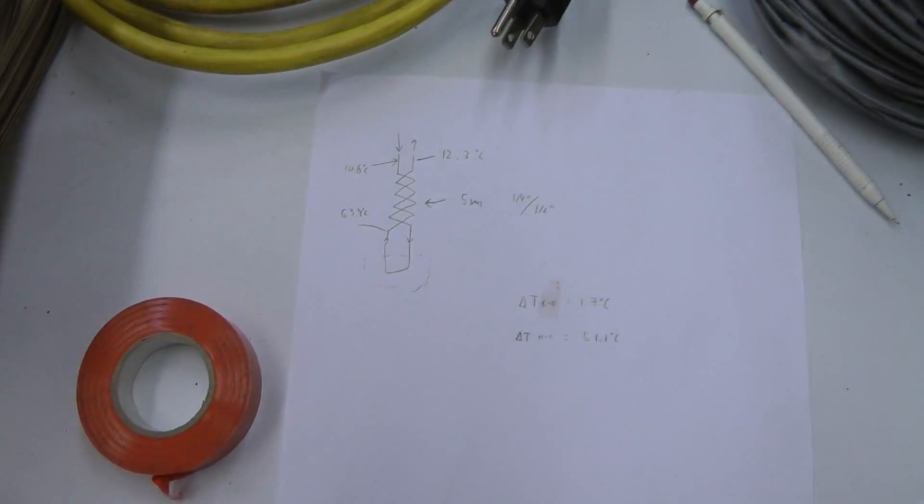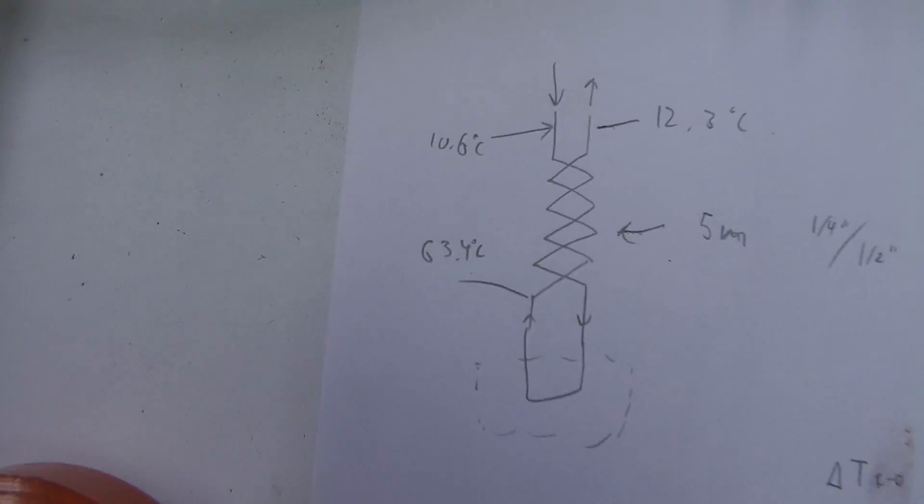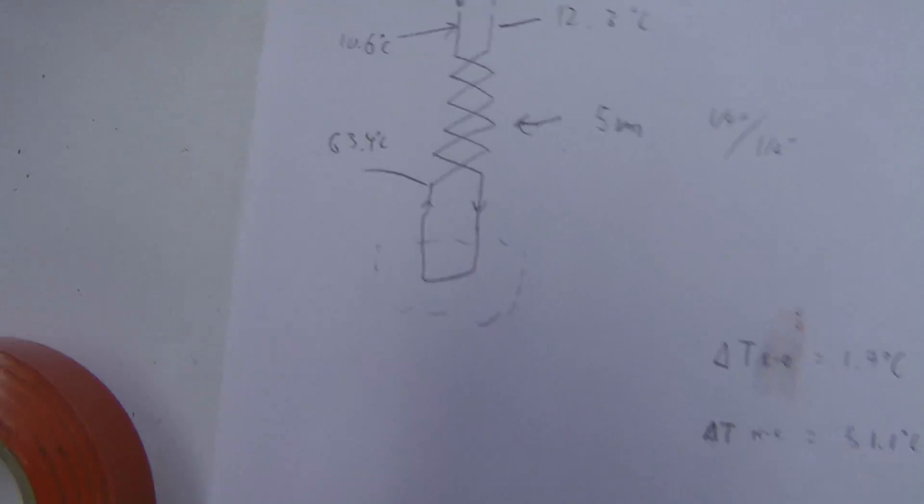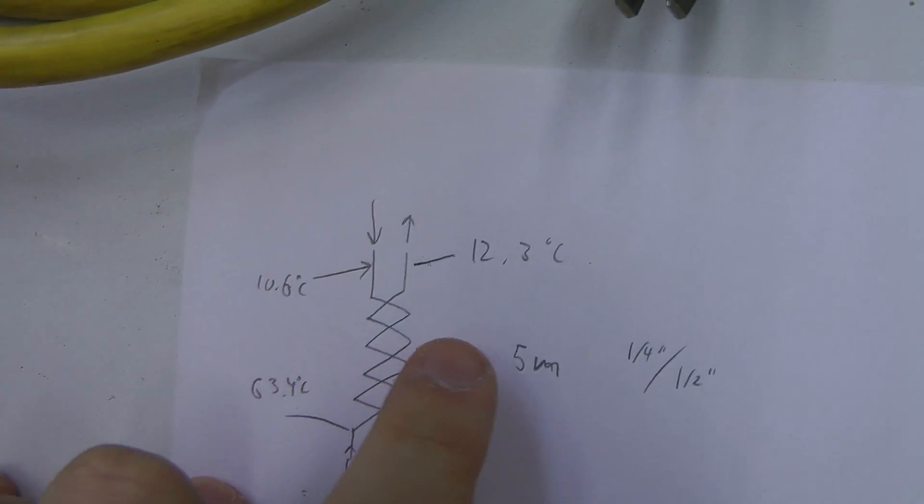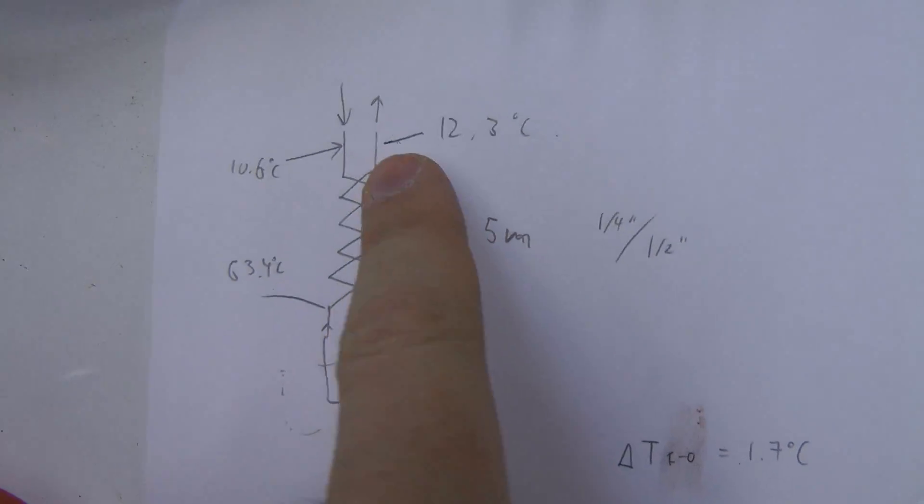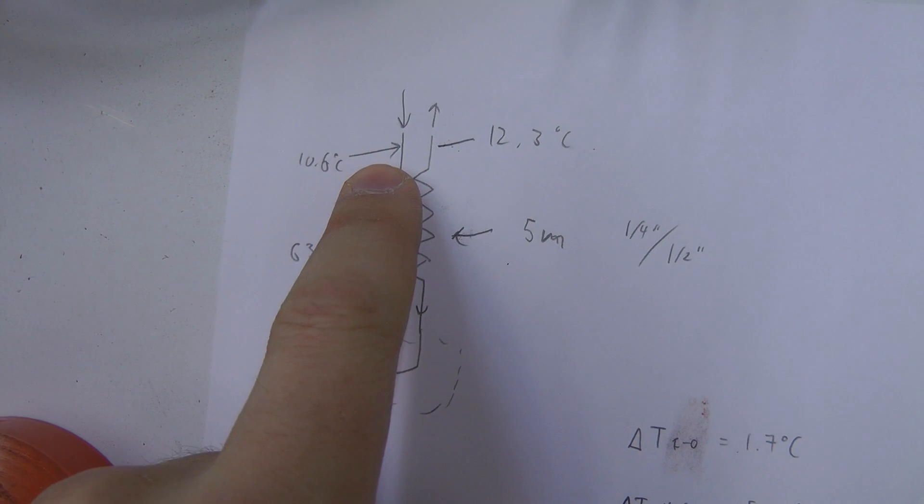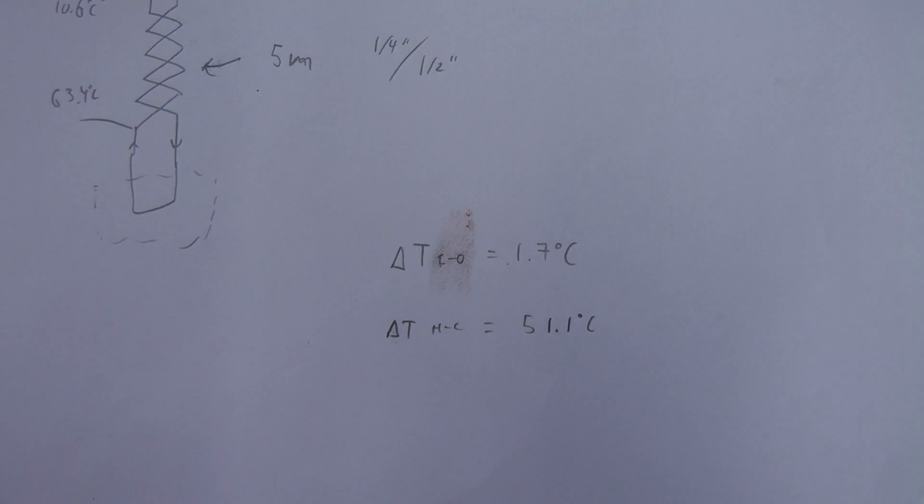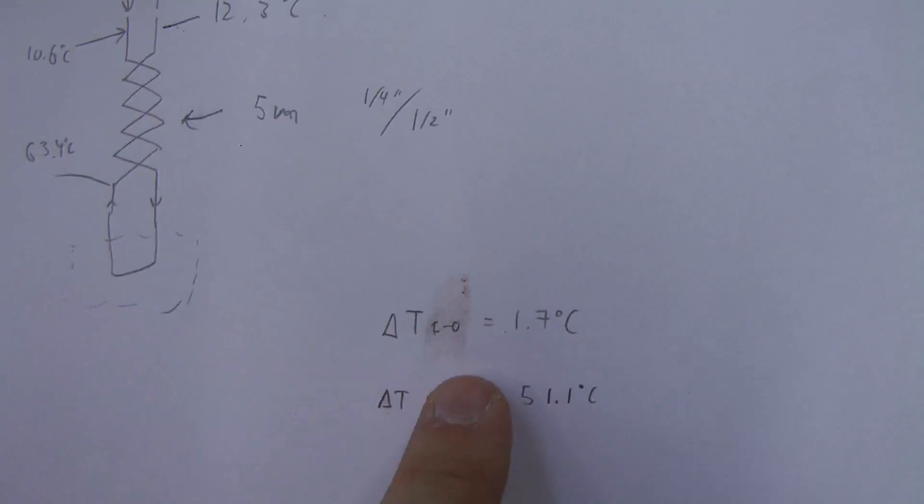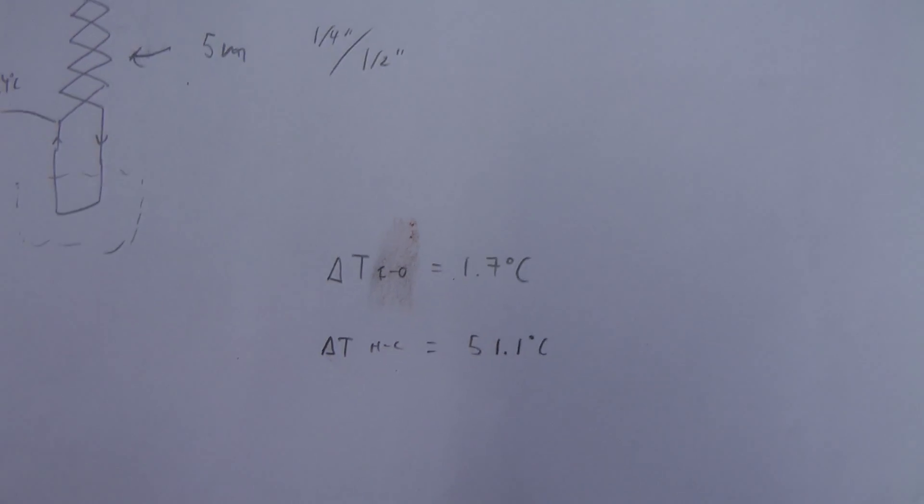Okay, the last measurement seems to have stabilized now. So the results are 63.4 degrees on the hot side, and 12.3 degrees on the exit, same gas, and the other two, the input tube, was 10.6. So we have delta T from the hot side to the cold side of 51.1 degrees, and delta T between the two input lines of 1.7.